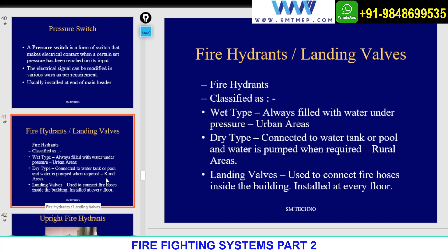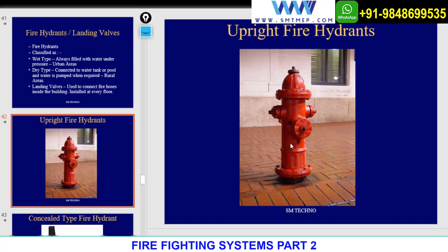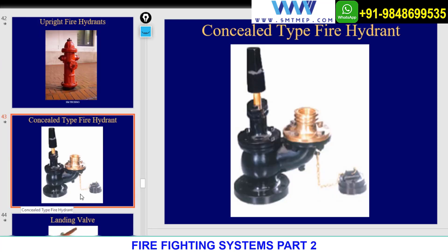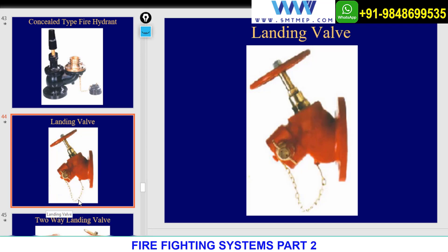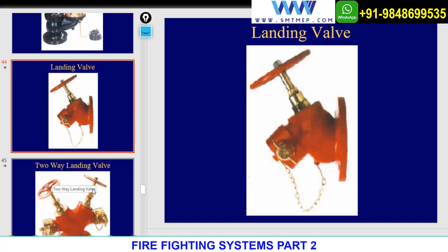Fire hydrants include stand post type and concealed type. Concealed type has a manual cover but is generally not recommended — the stand post type is most common. Landing valves can be one-way or two-way. A landing valve with a pressure regulating option allows you to set the pressure as per system requirements. The one shown on screen is a normal single-way landing valve.